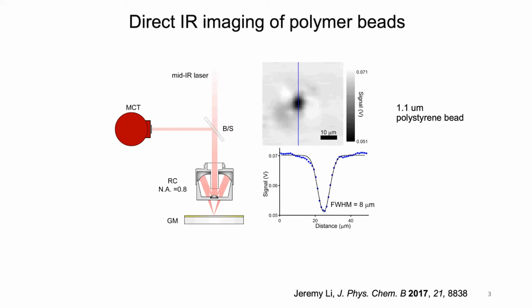So if you move the sample through the focus, you'll see an absorption by the bead, so a decrease in the reflected light. This is actually a pretty big signal. About 25% of the light gets extinguished by the bead, and you're just detecting that with a regular IR detector. The spatial resolution here is determined by a couple of things, as has been discussed by Jixing Cheng a little bit earlier and Ilya. The main effect is that you're using infrared light, so the diffraction limit is the wavelength divided by 2 times the numerical aperture. So it's not all that great.